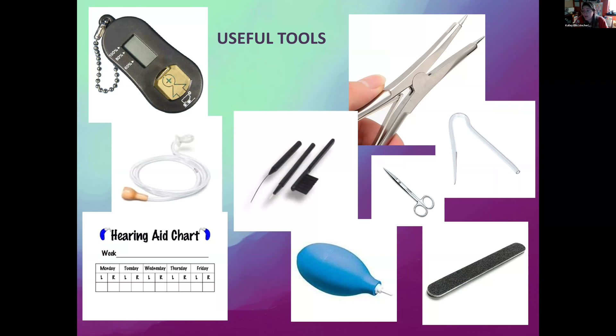Okay, so then let's say you detach the tubing from the hearing aid, and you're still not hearing any sound. Now I'm going to be looking at the microphones. Is there debris, something clogging those microphones? If there is, I'm going to take that little brush and wipe over those microphones. And then do a listening check. You always want to be doing a listening check after each step to see if it solved the problem.